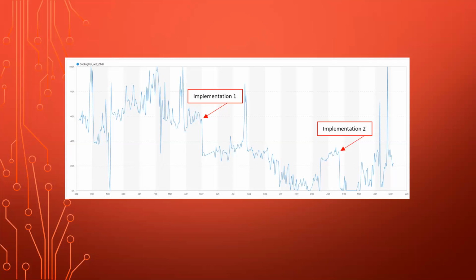There was a whole winter in 2018 where we never got below 60%, the valve being 60% open. Then with our retro commissioning efforts, we were able to reduce that down to what you'd like to see in the middle of winter, which is next to no consumption for chilled water. So this is how we're using this tool - one thing is to look at the impact our retro commissioning efforts are having on energy usage.